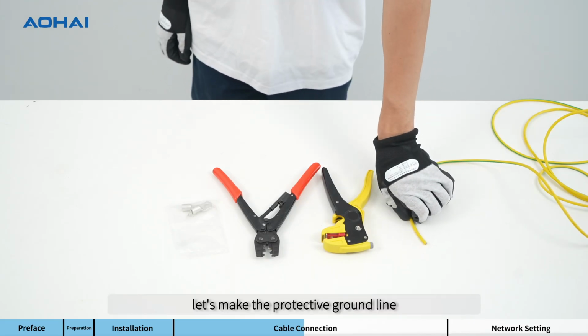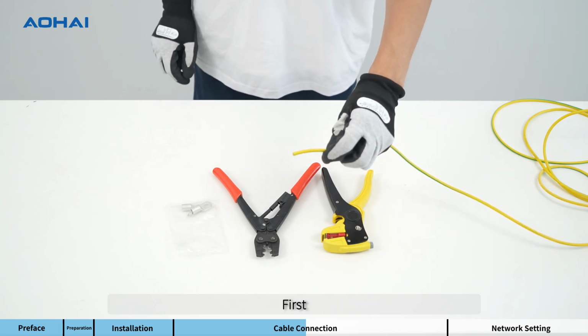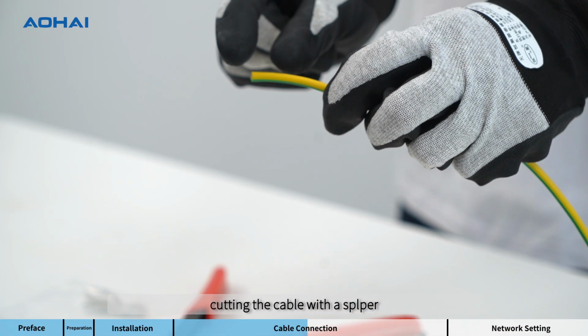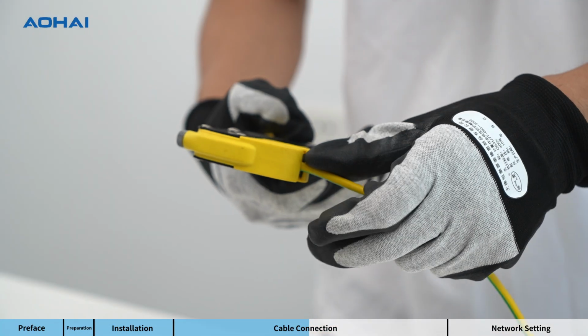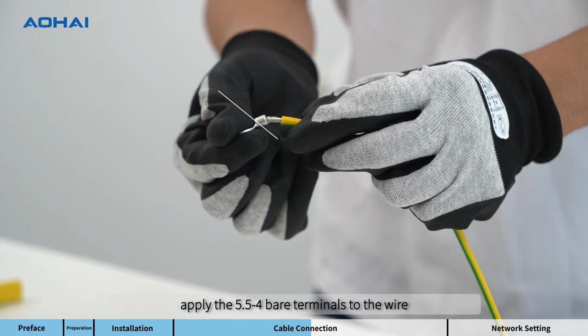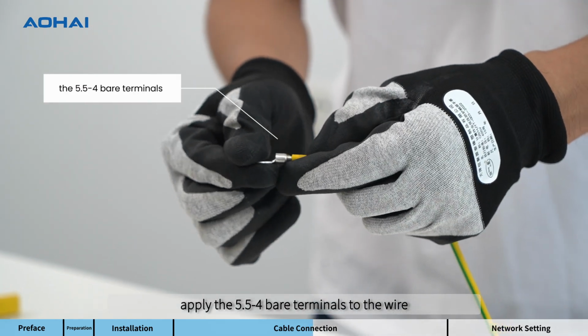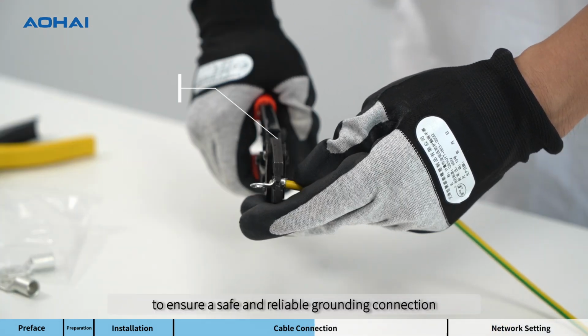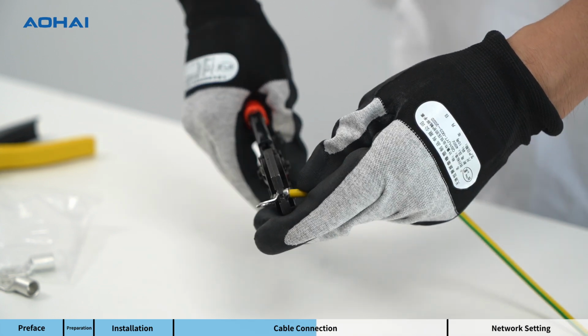Finally, let's make the protective ground line. First, cut the cable with a stripper and remove the skin. Then, apply the 5.5 to 4 bare terminals to the wire to ensure a safe and reliable grounding connection.